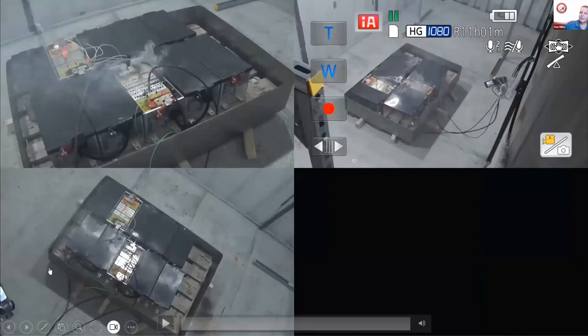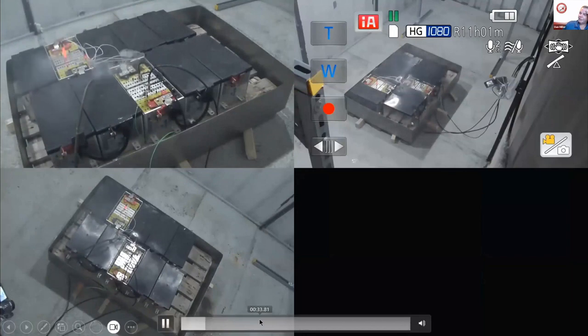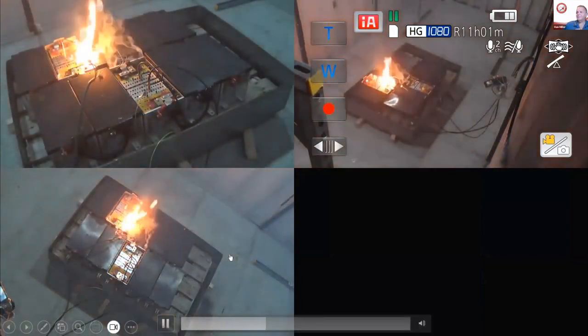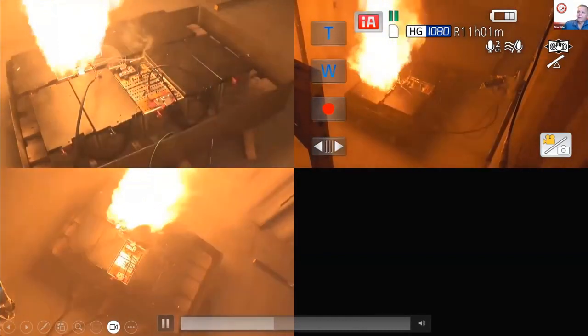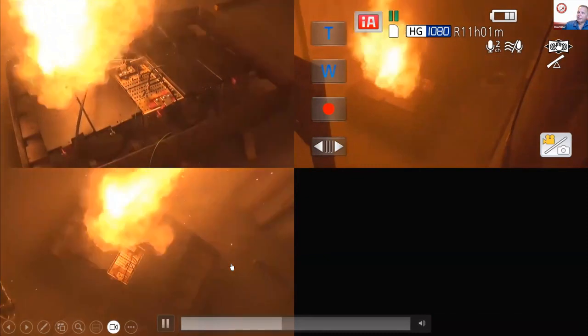This is that same truck battery module we looked at earlier, except now there are 10 modules. We start a couple of them on fire with glow plugs. These are 18650 cells, packed tightly together in these modules. In this test, there's a sprinkler system, but the sprinkler heads are offset so they're not directly impinging on it. They wanted to demonstrate that even without a real direct stream of F500, it would still be functional, and it very much is, as you'll see.